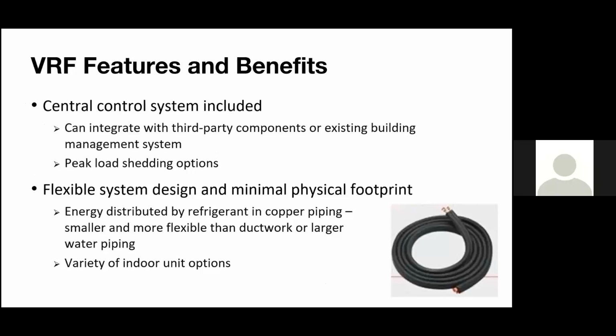If you're a larger building, if you have a building automation system by one of the larger controls companies, you can also integrate the VRF systems using this central controller. So we use a protocol called BACnet to be able to talk the same language as these automation systems. There's also options for peak load shedding with some inputs if you want to tell the system to limit itself, either for running on generator power, or maybe you're trying to do some peak load shedding with the grid, and all sorts of options with that, which make it pretty nice.